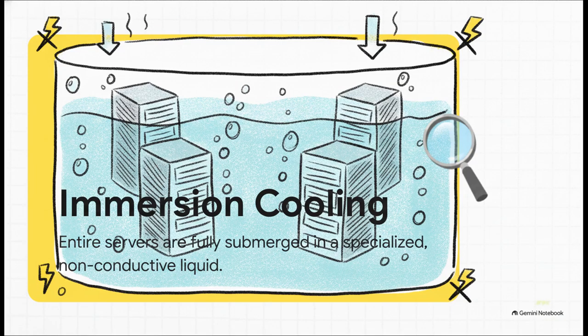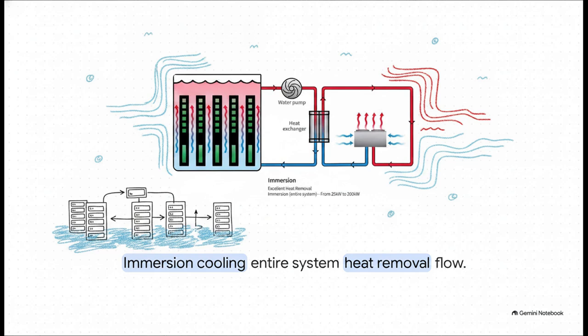Now, the second method takes things to the absolute extreme: immersion cooling. For environments dealing with staggering heat densities, or maybe confined spaces that just don't have traditional data center infrastructure, you literally submerge the entire server hardware into a tank. Use a highly specialized, non-conductive and non-corrosive fluid, of course, so it doesn't short out the electronics. The heat removal flow here is just brilliant. The submerged components directly transfer their heat to the fluid. As the liquid warms up, it naturally rises to the top of the container, where it's pumped out, run through a heat exchanger to be chilled, and then gracefully cycled back in. It is incredibly efficient. And the best part? It operates with virtually zero noise.